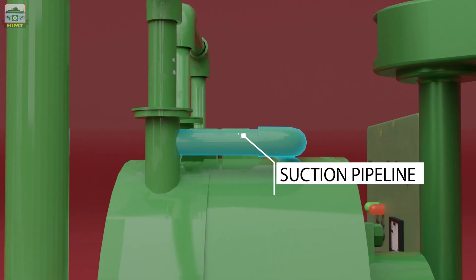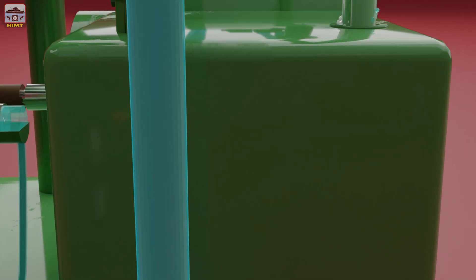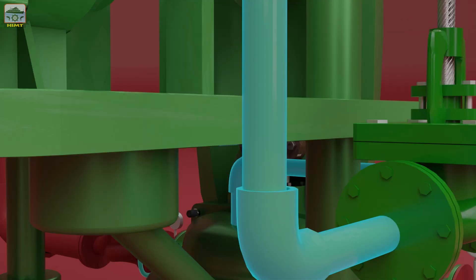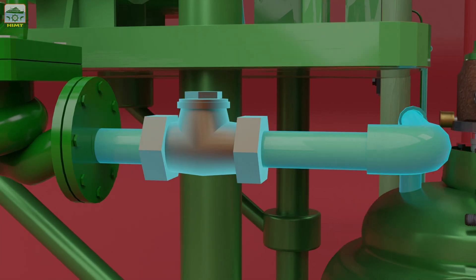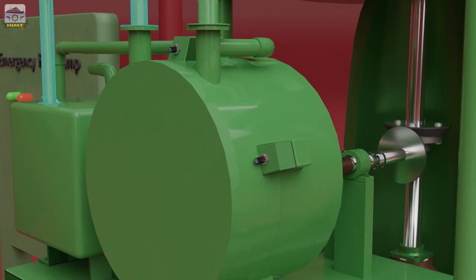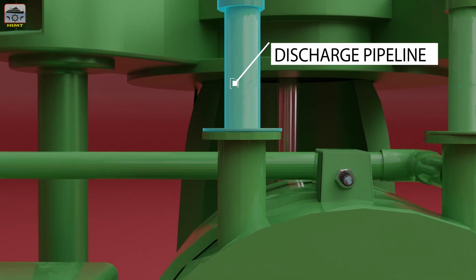The suction side of the pump is connected from the bottom of the water tank. The suction side of the pump is also connected via a non-return valve to the top of the centrifugal pump into the suction chamber. The discharge side of the pump is connected to the top of the sealing water tank.